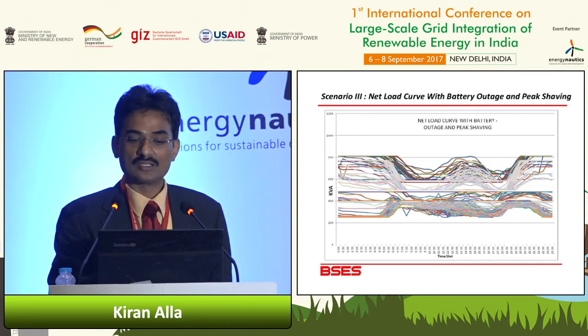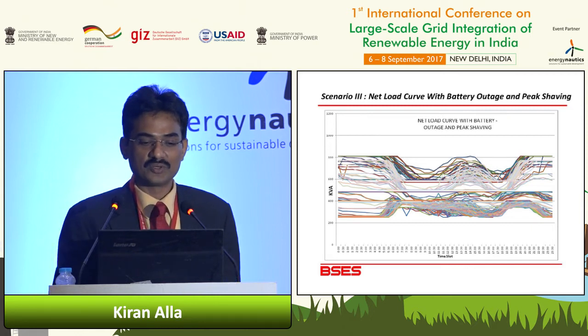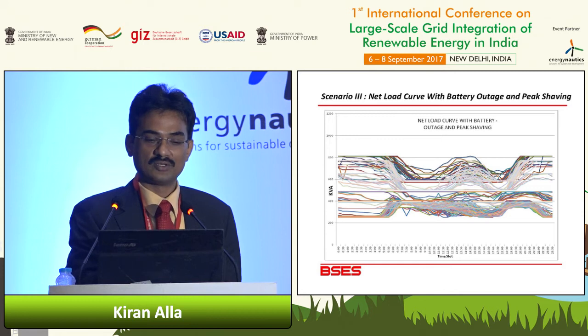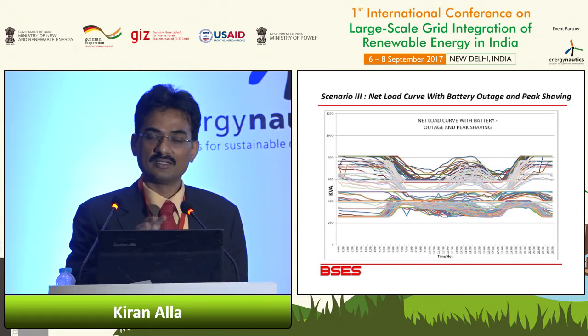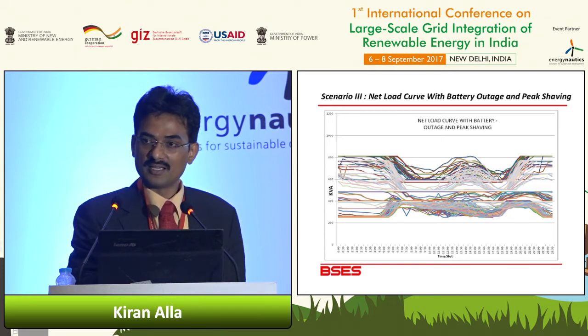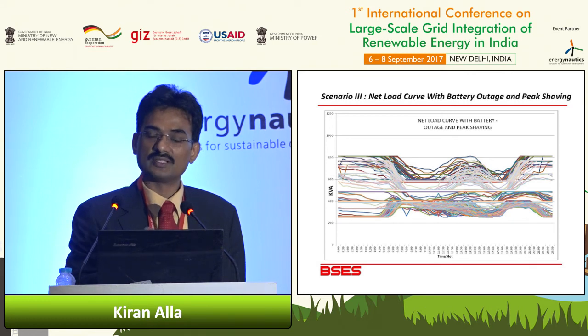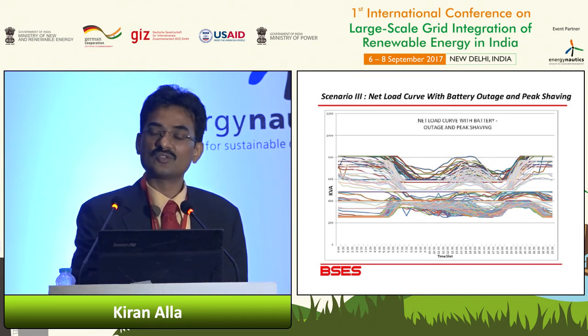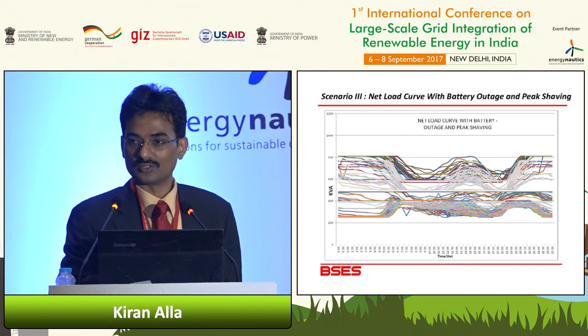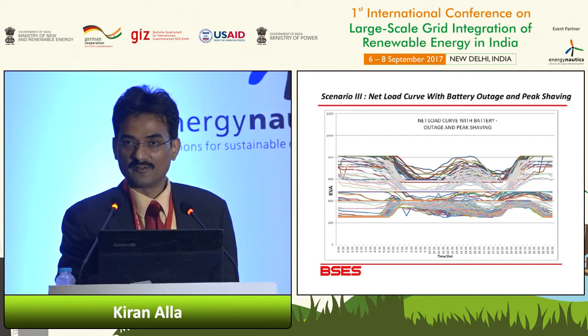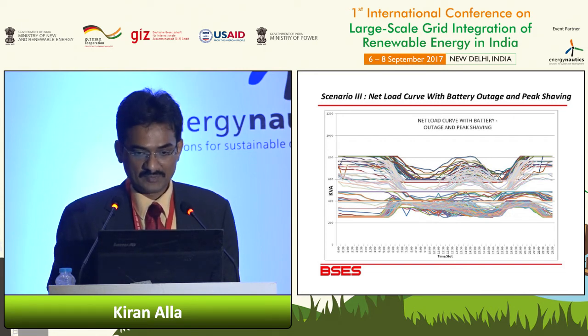You can also reduce the peak, shaving it up to 20%. So if it's a 1 MVA transformer, I can reduce my peak and optimize on that, because then I can defer my capex. That gives me another 5 years of load growth, meaning I can defer the capex by another 5 years.